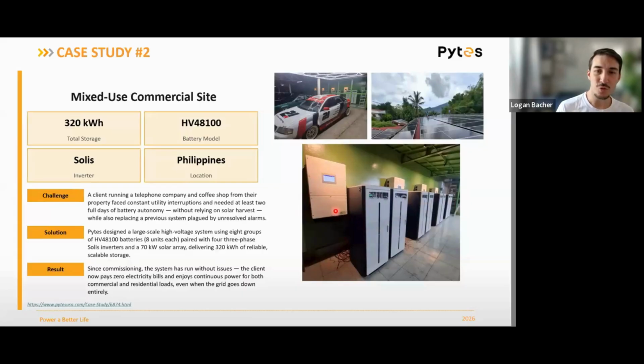The inverters have two battery inputs, and this applies to both Sol-Ark and Solis. Those battery inputs are completely independent of each other - we're actually not parallel connecting these two batteries. Each battery cabinet feeds independently up to an input in the inverter. That means your battery cabinets can, in certain cases, be charging and discharging at different rates, and have different states of charge. That's because the two inputs inside the inverter are isolated.